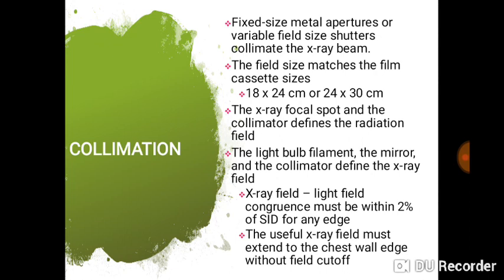There is collimation of the beam, just like any radiographic procedure employing ionizing radiation, which is harmful on exposure to living cells. It is important that collimation is adequate — the field size matches the film cassette size so you don't expose beyond that. The light bulb filament, the mirror, and the collimator define the X-ray field.